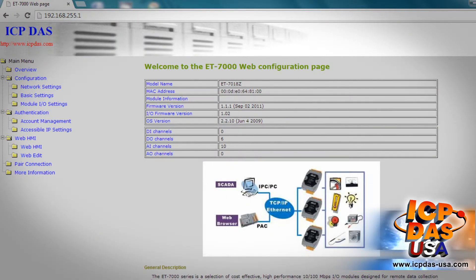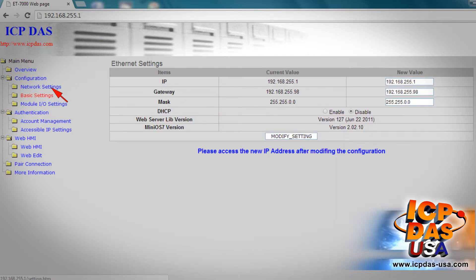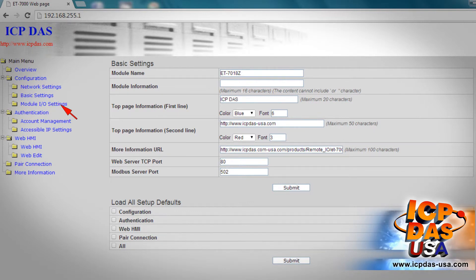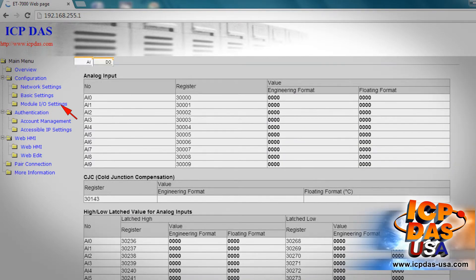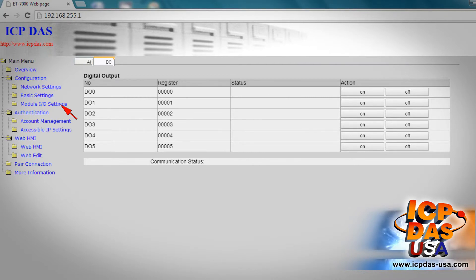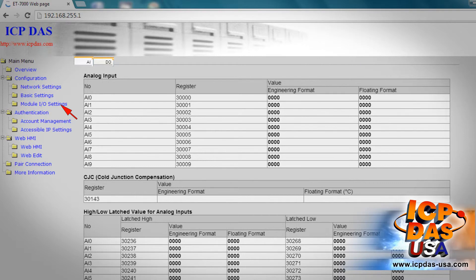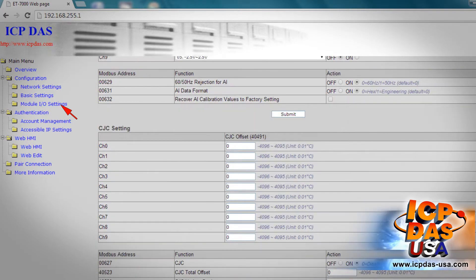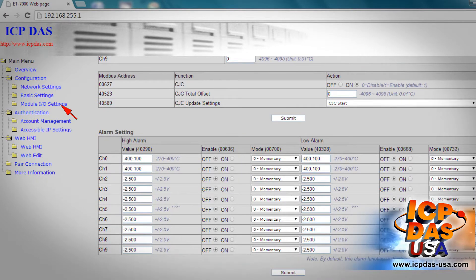This is the ET-7018Z's web interface where we can adjust the module settings, IO settings, and monitor the inputs and outputs. We can set our Ethernet settings here. The basic settings include the module's name, module information, web server, TCP port, and Modbus server port. The module IO settings include digital output channel on/off positions, safe value, analog input settings like input range values and channel on/off positions, cold junction compensation settings, and alarm settings.